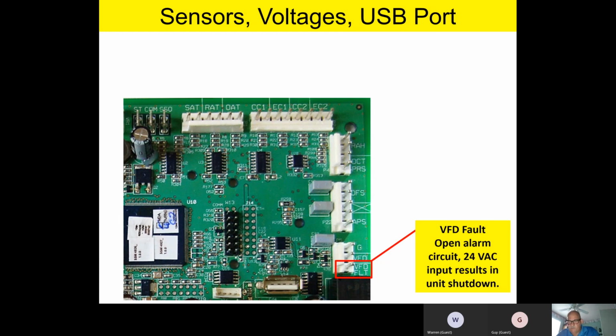And if I apply 24 volts AC on that VFD fault pin, it shuts the unit down. So it's kind of opposite of what you think an alarm circuit would be. We normally think about alarm circuits being normally closed, and then they open for alarm. Well, this is exactly opposite. Open circuit is normal. If I put 24 volts on it, it shuts the unit down. Any questions or comments on that? So if I take my voltmeter and everything's running good, I should not read voltage on that VFD. If I've got a variable frequency drive, I should not read 24 volts on that alarm circuit when it's running normal.